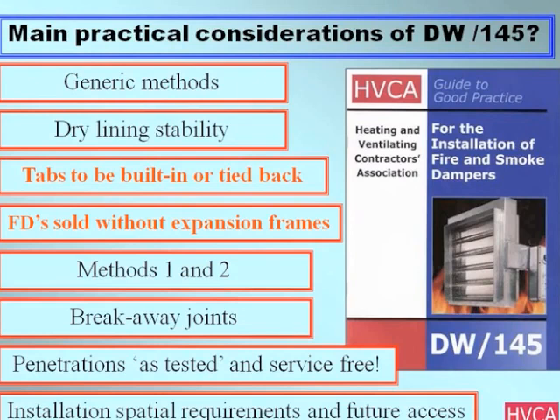Another big aspect is the spatial requirements to fit a fire damper. This isn't just about the time of fitting—it's also for future access, so that during the building's daily use, regular tests can be carried out, including damper blade drop tests. It's important that all this is planned into the design.